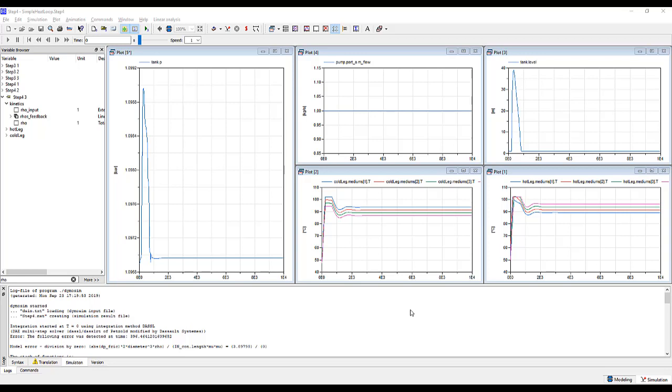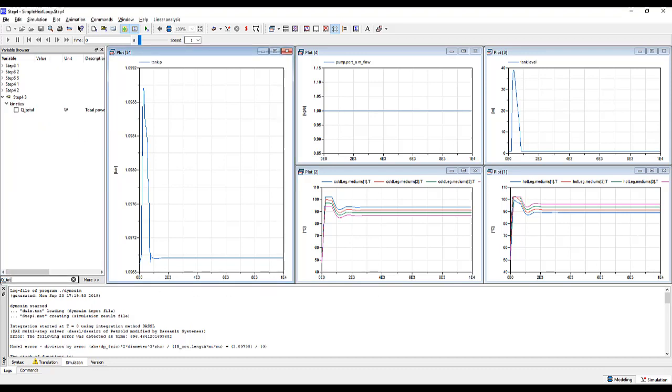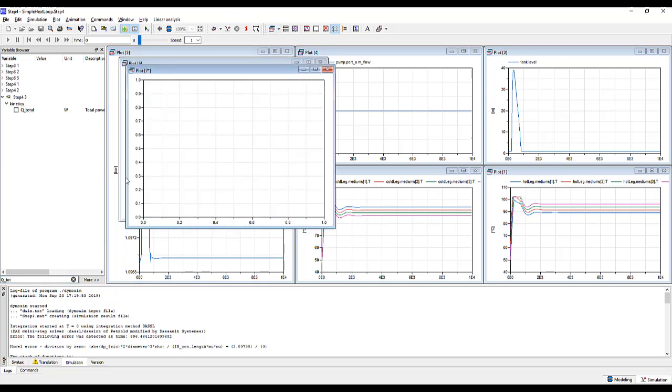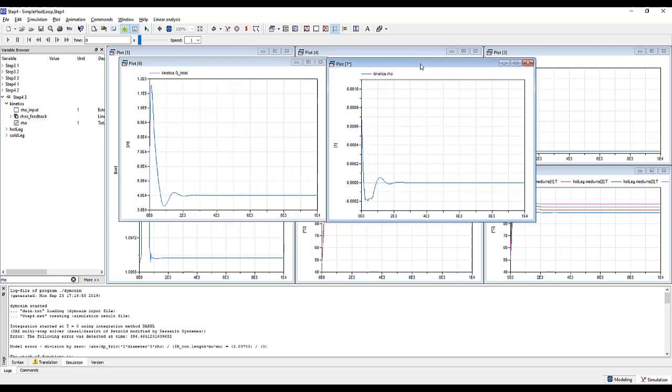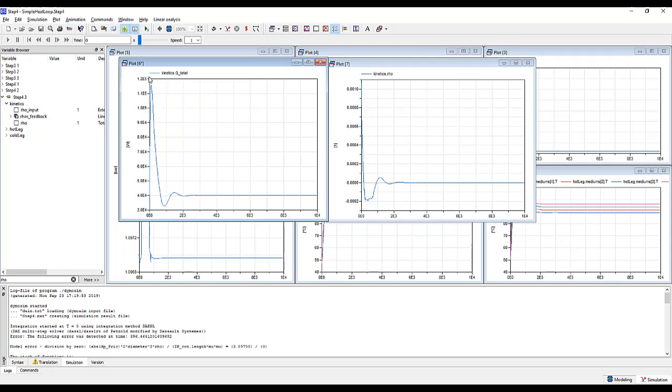As we look at our results, there are two distinct regions. Beyond 4,000 seconds, with steady state condition reached. And before 4,000 seconds, particularly at the beginning, where we have a spike in values. Now this spike is associated with the temperature feedback. We gave a reference value of 92.67 degrees Celsius, but that was pre-calculated, associated with a steady state value. This means that at the beginning, we have a lot of feedback going into the nuclear kinetics, changing the power level. To investigate that theory, we can go ahead and plot the power and the reactivity of the reactor. As we look at these, the power level has increased significantly at the beginning, and that's associated with this large reactivity insertion. As things balance out, the reactivity goes to zero, and the power returns to the value we expected.